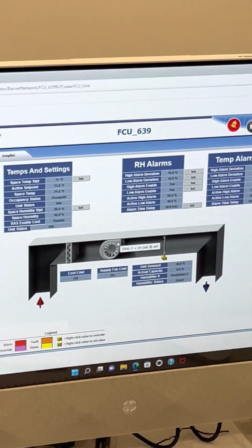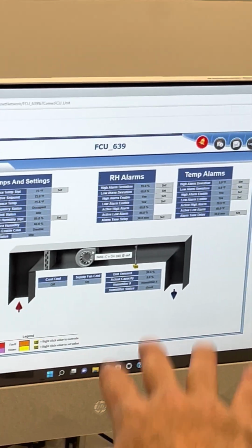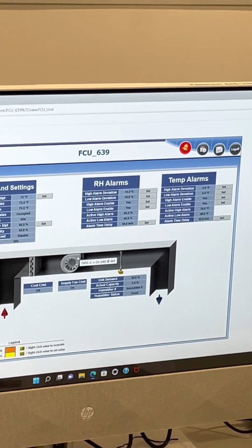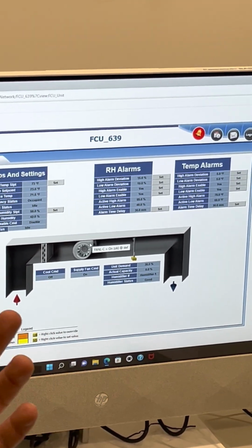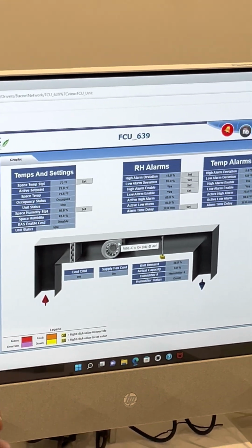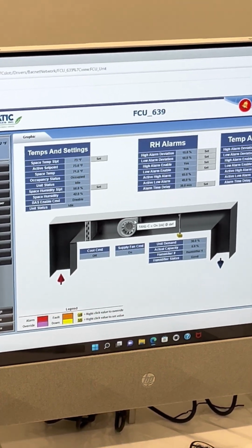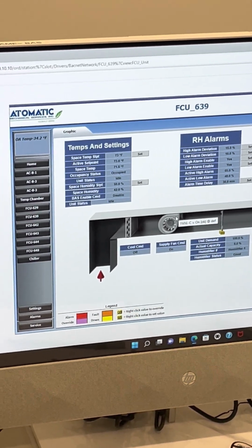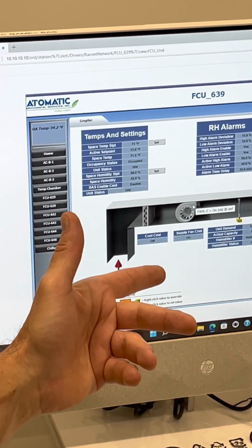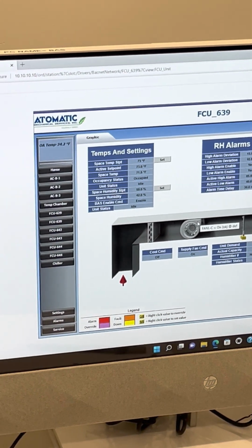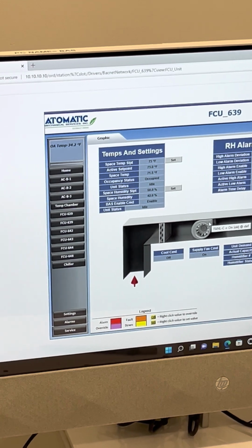Generally, we wouldn't put that in there. You know what I'm saying? Generally, we would just let it float. But since we had a couple of things, I just took it upon myself to put at least a high stopgap on there, give it a little time out, and come back down. But if the humidity was below 40 at that point, it would have automatically enabled for us. Right now it was still disabled because we were above. It's reading 42% in there.